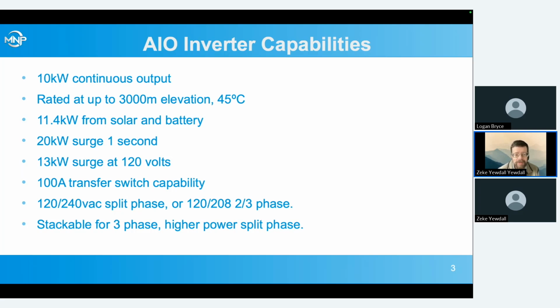11.4 kilowatts when we've got solar and battery. The 10 kilowatt is on battery alone. So for battery backup design and off-grid design, that's the realistic number, assuming you may be operating at nighttime. 20 kilowatt surge for 1 second.